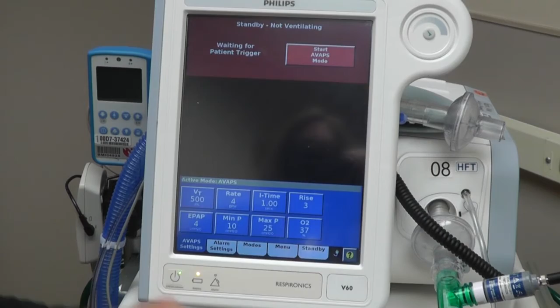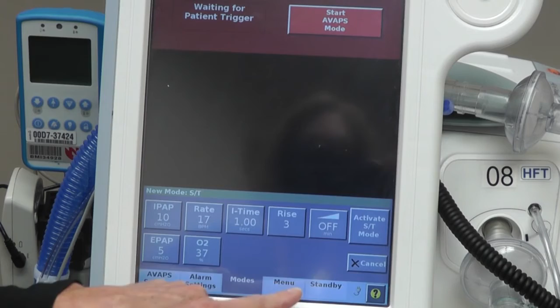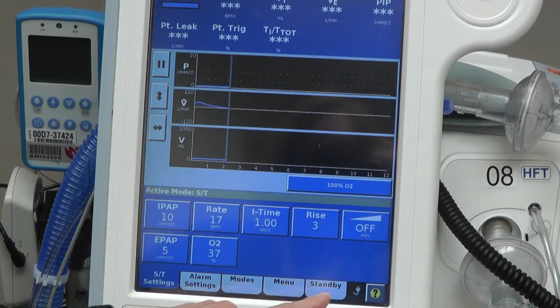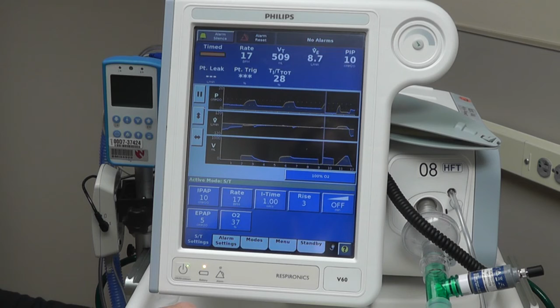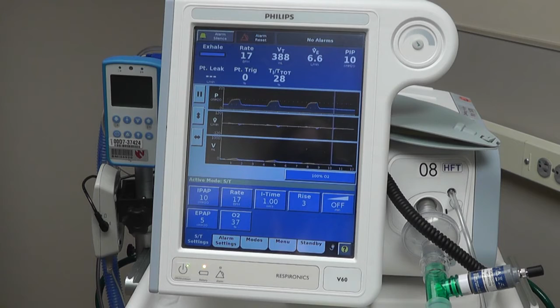Going back to standby, we can go back into ventilating our patient, and I'll pick the ST mode that we're used to seeing and activate that. And then start. So anytime you're in standby, you can restart it by hitting the start button again, and then your patient will be in the mode that it was in when you put it into standby. If the machine does get powered off, when you turn it back on, it will be in the mode that it was on when the machine was turned off. It's just you'll see total leak here instead of patient leak. And that is an important feature of the V60, to be in the patient leak here. So entering standby is the way we want you to do it for this machine.